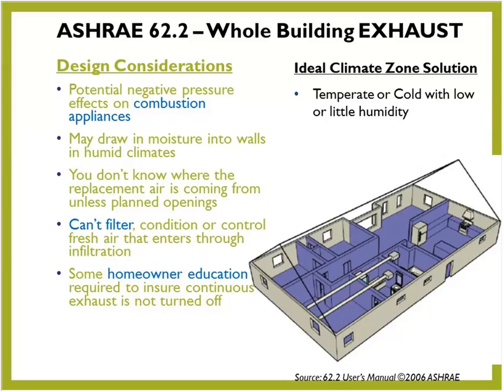Years ago, it wasn't uncommon for fans to be vented to those little silver vents that were in the soffit, which have basically a window screen in them, and they would get plugged and really choke down the fans as well. So we've certainly come a long way since then, and people understand more about the static pressure, and making sure that we're using a good termination as well.